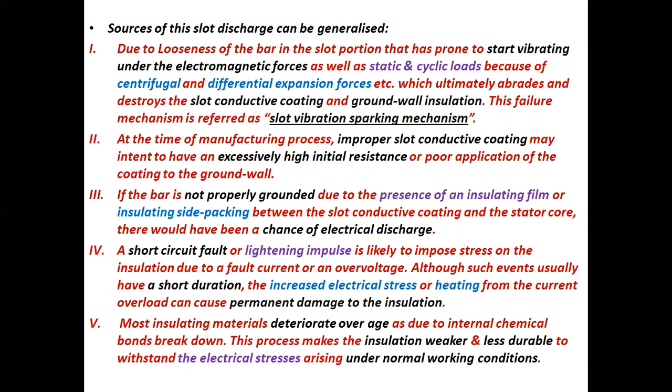Number three, if the bar is not properly grounded due to the presence of an insulating film or insulating side packing between the slot conductive coating and the stator core, there is a chance of electrical discharge. Number four, a short circuit fault or lightning impulse is likely to impose stress on the insulation due to a fault current or an overvoltage.